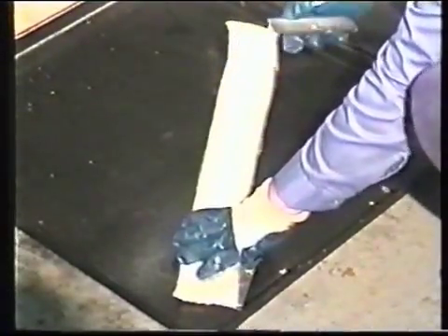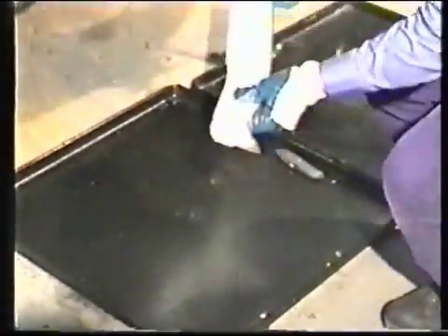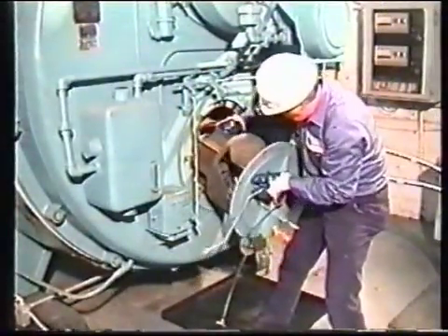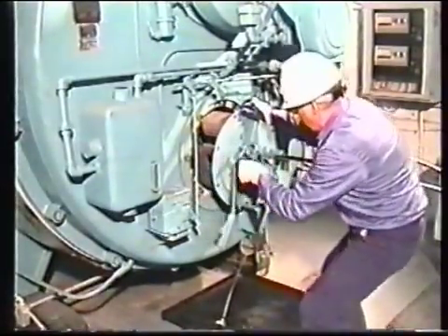To apply the Boiler Lizard, slip the long tube-like bag from end to end and place it in the dry boiler. It is recommended that bags be placed no farther than 10 feet from the metal surfaces in need of protection. After placing the Boiler Lizards, seal all openings. The corrosion inhibitor powder will migrate and protect metal surfaces within one hour. When the boiler is put back into service, simply fill with water and begin the normal start-up procedure — the bag will dissolve.